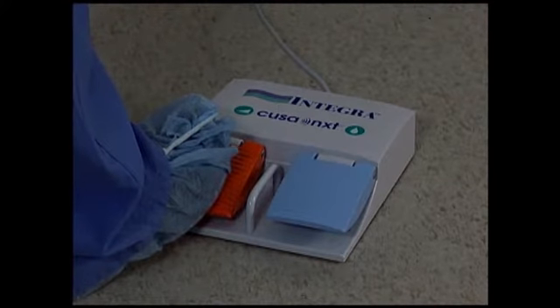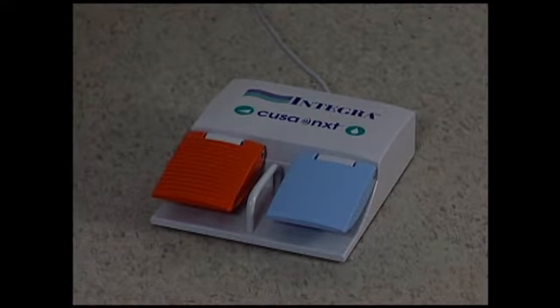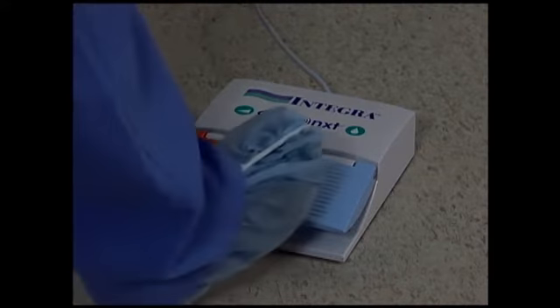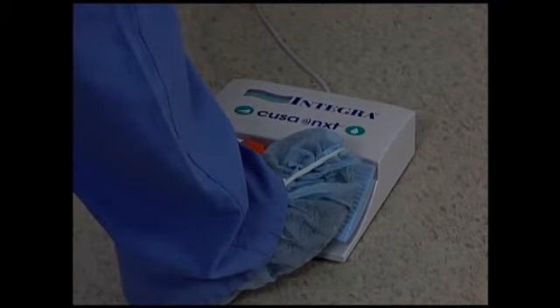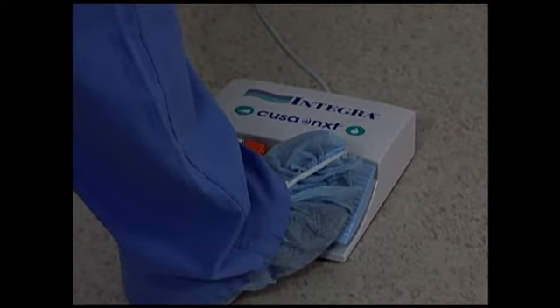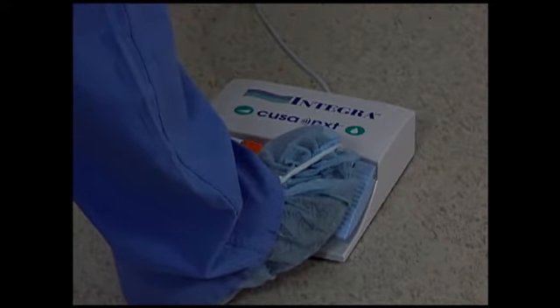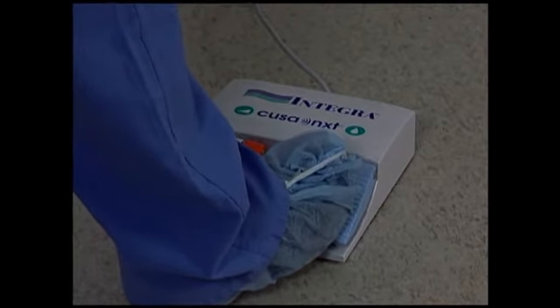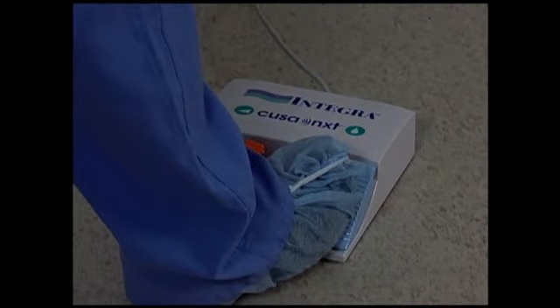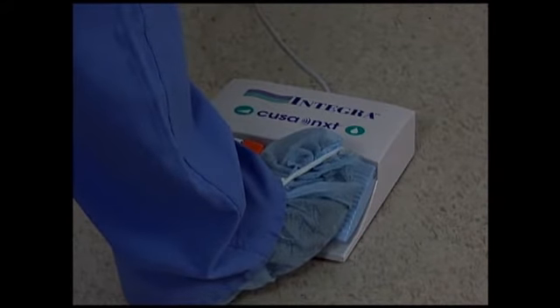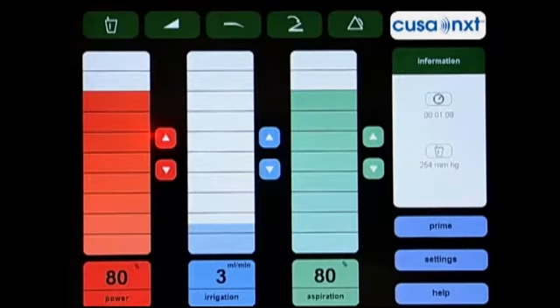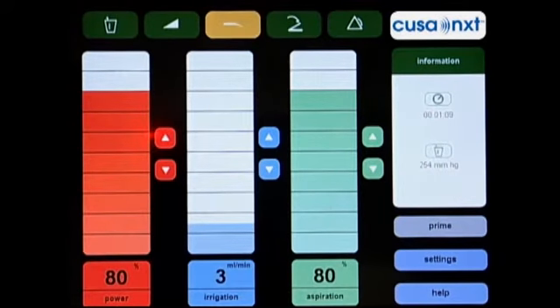console. To deliver a bolus of fluid, the surgeon depresses the blue irrigation pedal on the right side of the foot switch. Like the power pedal, the rate of irrigation delivery is proportional to the distance the irrigation pedal is depressed, up to a maximum rate of 50 milliliters per minute. Should a system error occur, the appropriate green indicator will turn to yellow and an alarm will sound.